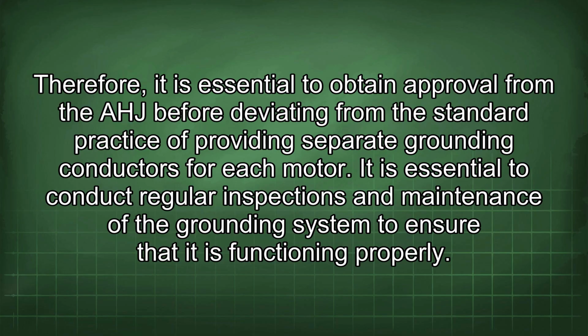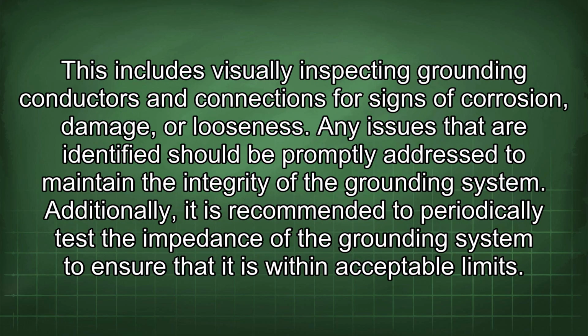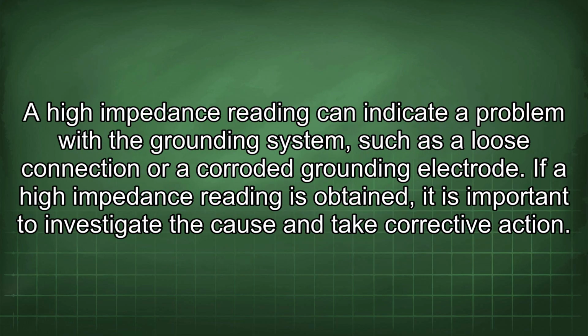It is essential to conduct regular inspections and maintenance of the grounding system to ensure that it is functioning properly. This includes visually inspecting grounding conductors and connections for signs of corrosion, damage, or looseness. Any issues that are identified should be promptly addressed to maintain the integrity of the grounding system. Additionally, it is recommended to periodically test the impedance of the grounding system to ensure that it is within acceptable limits. A high impedance reading can indicate a problem with the grounding system, such as a loose connection or a corroded grounding electrode.